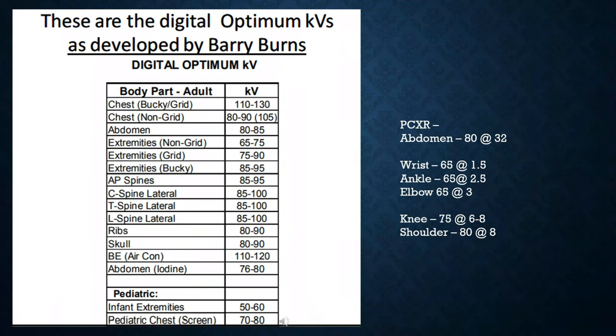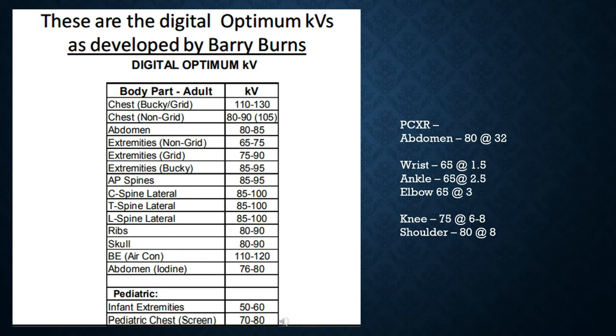The new digital optimum KVs to get the best picture are going to be a little intimidating and scary for techs who have been in the field for a long time using such high KV. This is generally needed to lower the mAs and lower the patient dose. Looking at this chart, the C-spine was generally between 85 and 100 KV. These are the optimum KVs that compensate with the mAs in the system to still get an optimal diagnostic image readable by the radiologist.